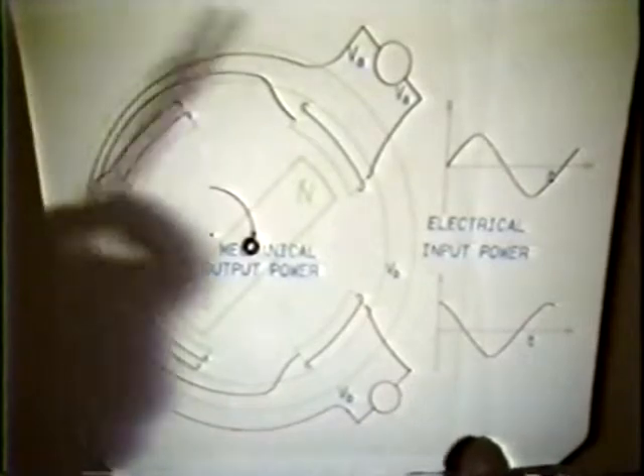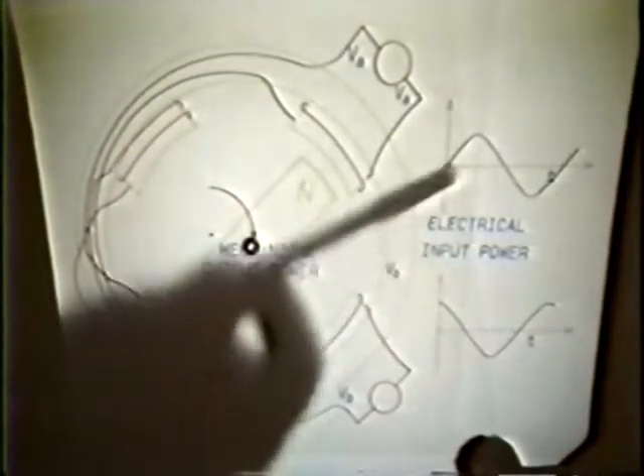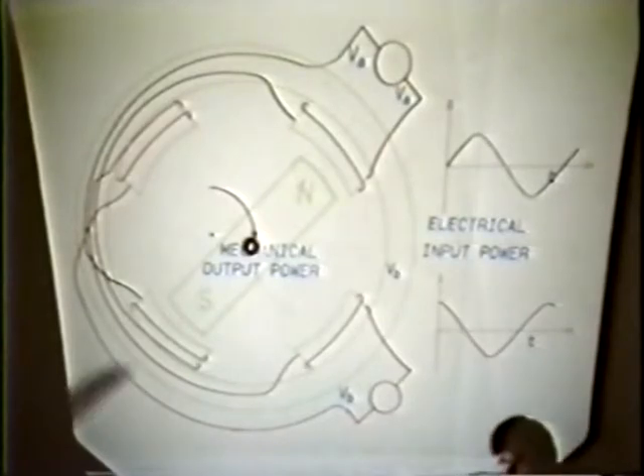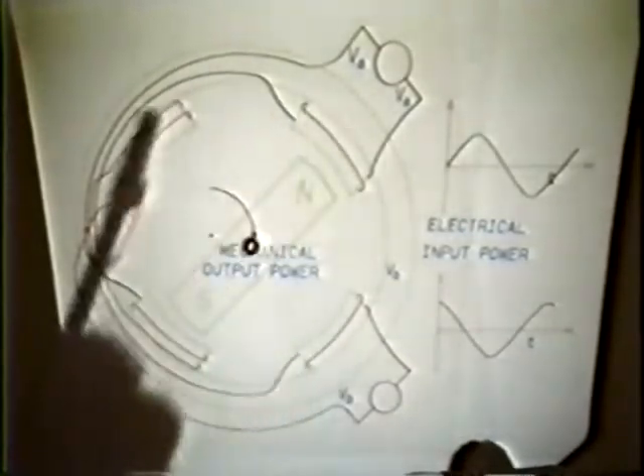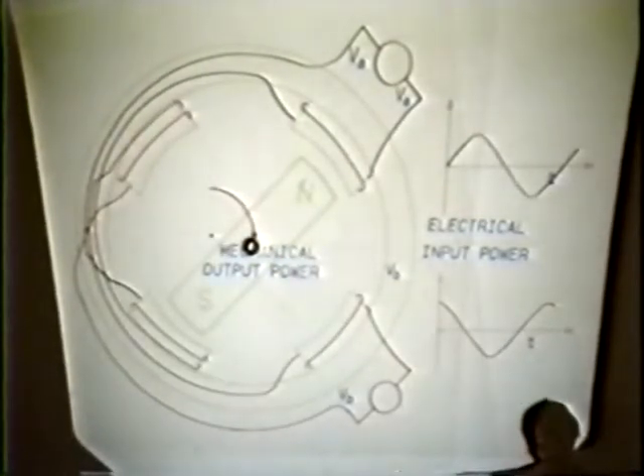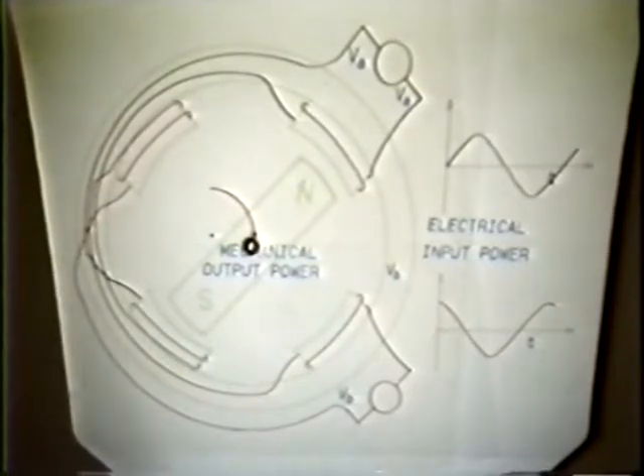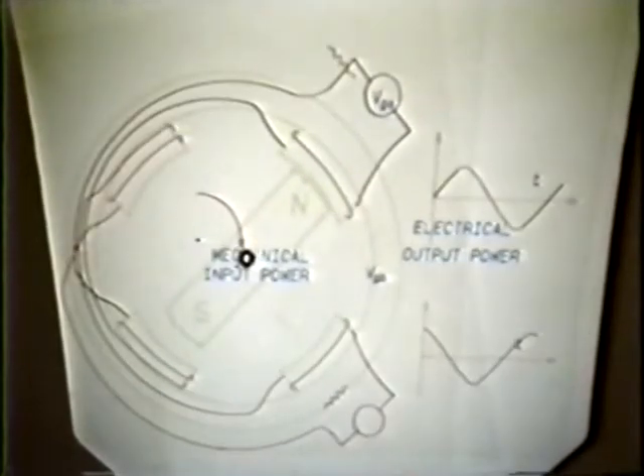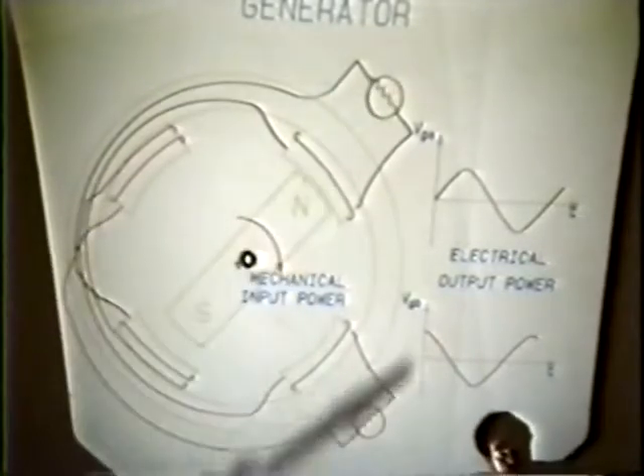A synchronous motor moves at the speed which is exactly proportional to the frequency of the currents. For example, if you have 60 hertz currents which were adopted early on, that means 3,600 revolutions per minute. By putting larger numbers of different sets of windings, you can make a four-pole machine and then operate at 1,800 rpm. So you can have a single machine which is either the generator, two-phase generator, where you are putting mechanical power input, rotating it, and creating two-phase power out. This is the basis.